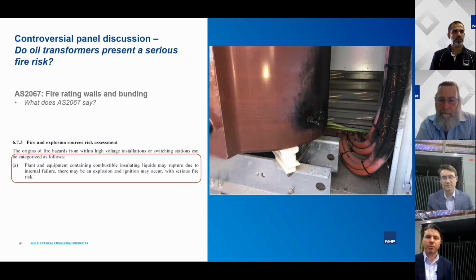So, Dimitri, maybe if we have a look at this, it doesn't look anywhere near as dramatic as what we saw in the video. But what can you tell us about this example? What happened with this cast resin transformer, and maybe why didn't it go the same way as the oil transformer video we just saw? Yep. Thank you, Nick. Yeah, that's a very good example of how a cast resin transformer behaves in the event of an internal fault. And the main factor to keep in mind is the calorific energy available in that device.